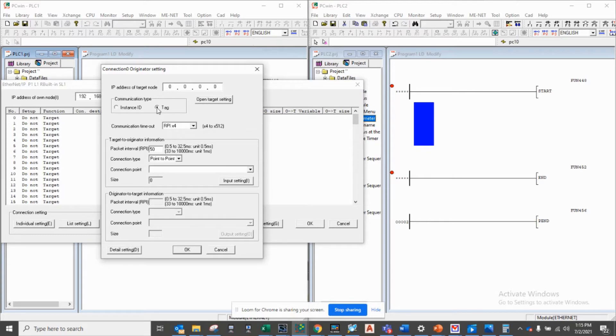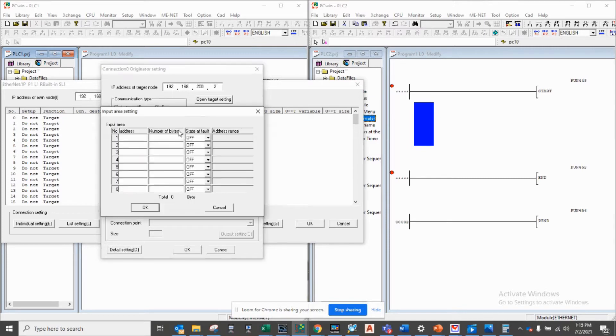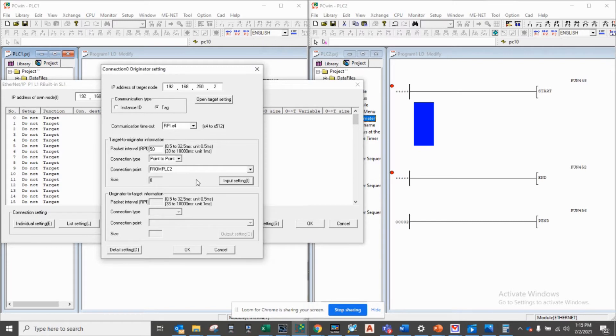I'll set up the target. I will be using tags. The target that I'm going for is 192.168.250.2. My tag will be from PLC2. For input settings, the information that I want coming in will be EM036L, 8 bytes forward. This is the range that the information will be coming to.